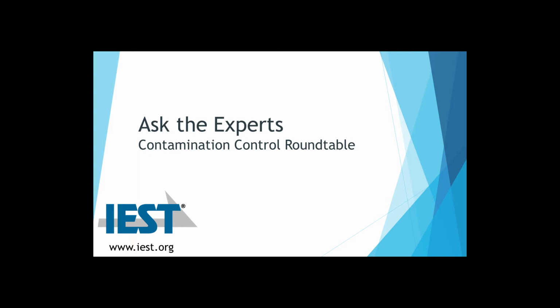You go ahead, Morgan. Okay, so the frequency of your cleanroom classification is per ISO 14644 Part 1, the second edition, 2015. Every cleanroom needs to go under cleanroom classification testing on a yearly basis. The caveat to that is if you're making sterile medicinal products, a sterile facility needs to be reclassified twice per year.